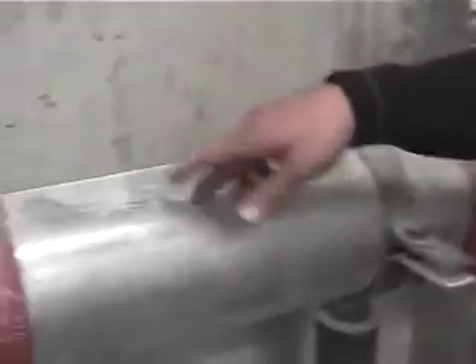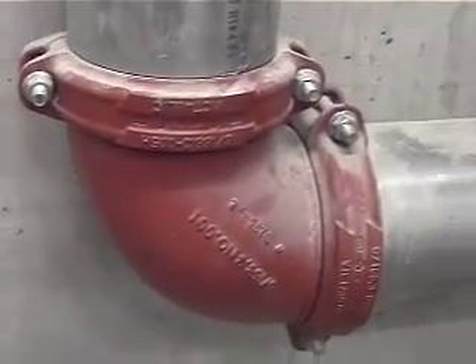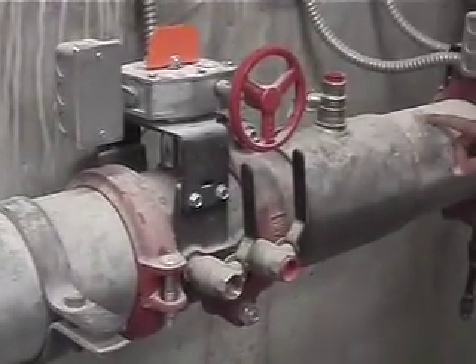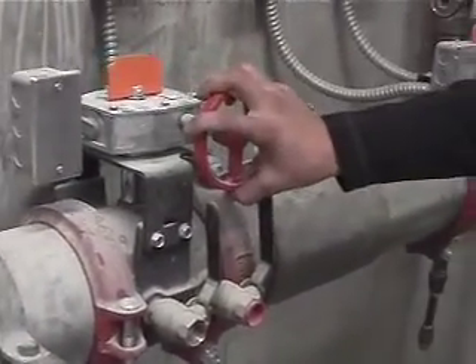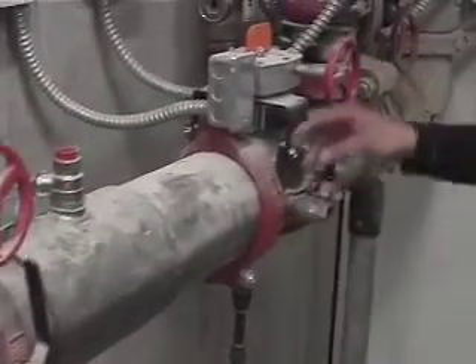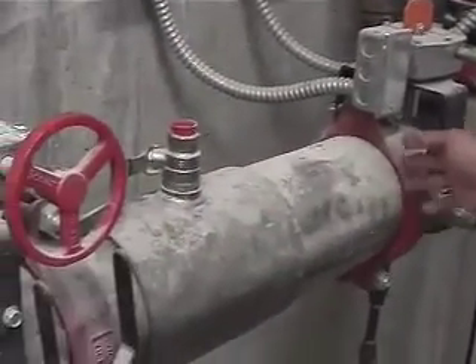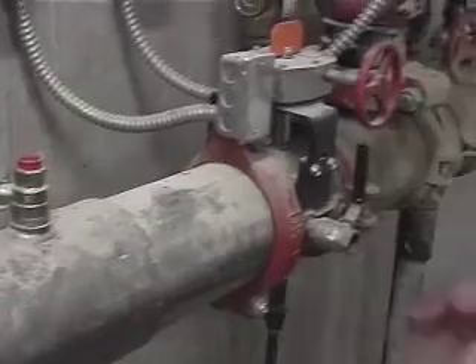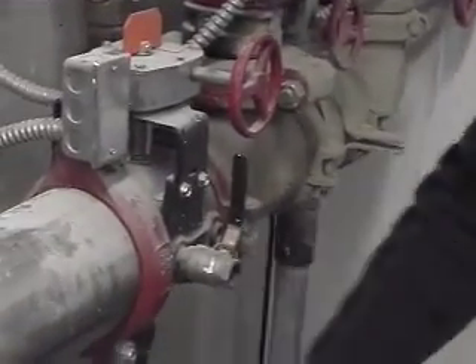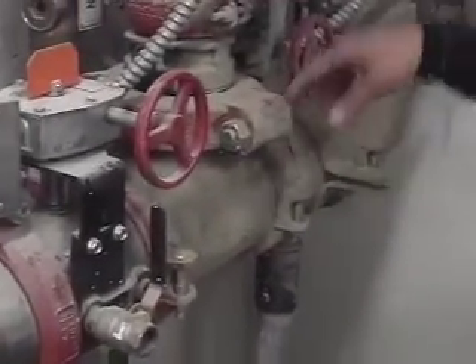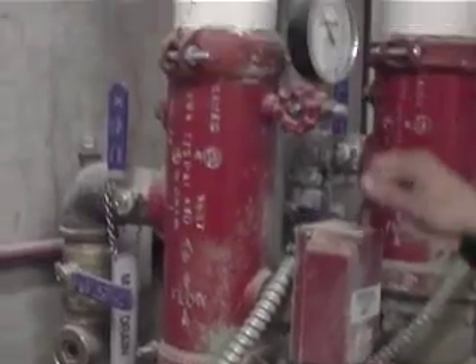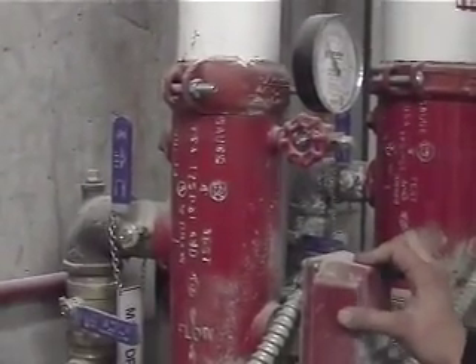East wing, basement side of the east wing. This is your underground supply coming in from the tunnel out by the PIV that we just looked at. You have your Ames backflow preventer, you have a control valve, your backflow assembly is actually from here to here. You've got all your test ports. After that you'll have your riser manifold. This feeds the basement zone for both sides and the tunnel.